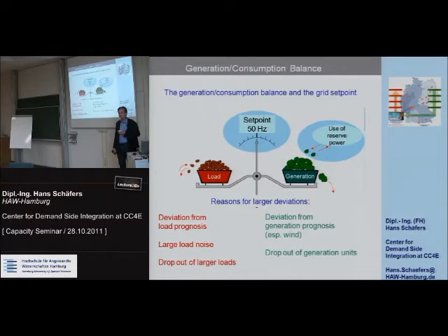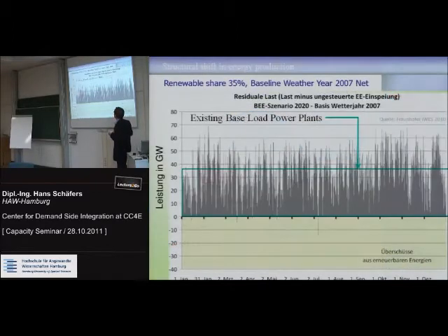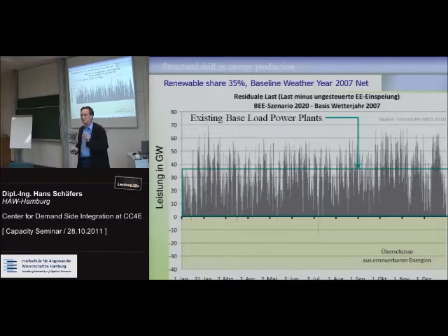Right. There will be a balancing effect with neighboring countries running these big loads. Right. Yeah. That is not taken into consideration here. And that is because at the interconnection points, actually, there is a certain amount of exchange possible, but it's limited. I'm not aware of what the limit actually is, but it's a couple of gigawatts, actually. So it's not possible to actually import all the amount that will be needed in these 2, 3, 4, 5, 6 hours, and then a couple of hours left after that, export anything that's in here.